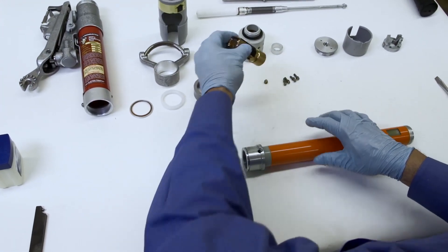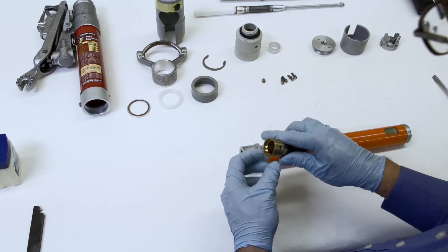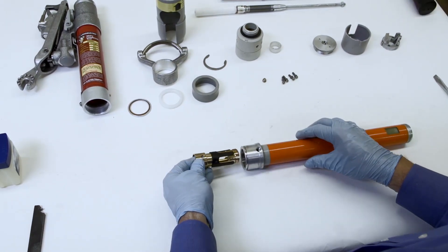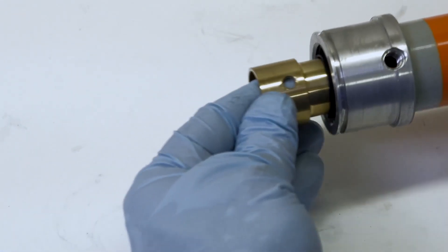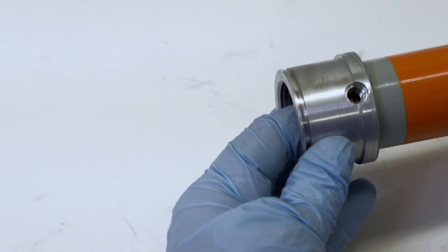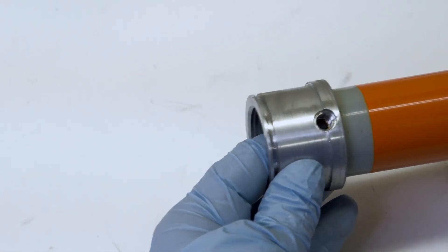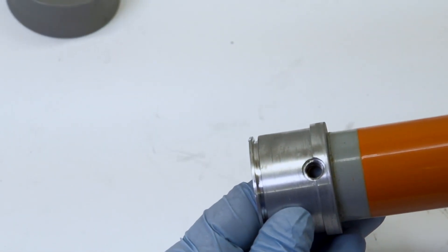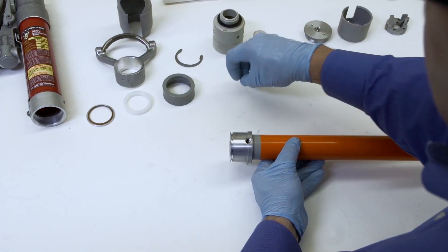To reassemble the Loadbuster Load Break Tool, first insert the stationary contact into the inner tube assembly, lining up the hole in the stationary contact with the inner tube assembly's tapped hole. Use a 5-32 inch Allen key to install a new socket head set screw.